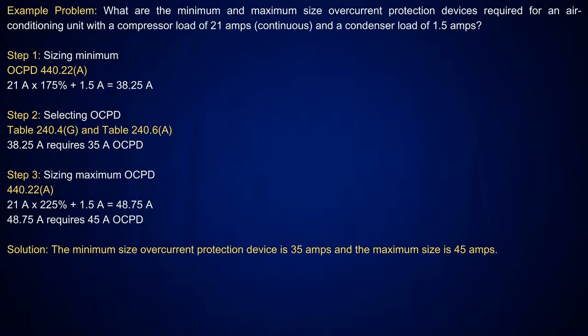Right. Now, the other thing I'll say here is this is just like motors. When I do a motor, you take the largest motor at 125%. All other motors are added at what? 100% for sizing the conductors. The same thing applies here when I'm doing the overcurrent device. You take the largest at 175% in this case, for the AC unit, and then you add the condenser on at 1.5 amps. So I take 21 amps at 175% and add that 1.5 onto it. That gives me 38.25 amps. Now, I just read to you, it says it can't exceed the calculated value. So I look at table 240.6A, and the next size below that is a 35 amp.